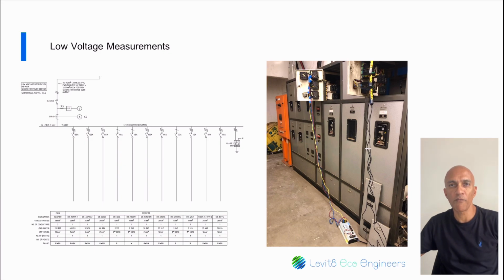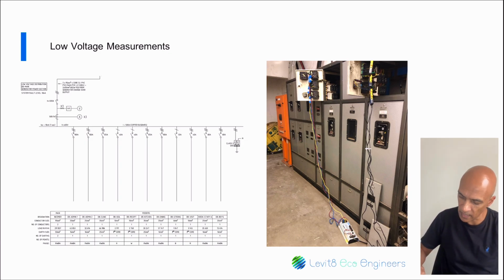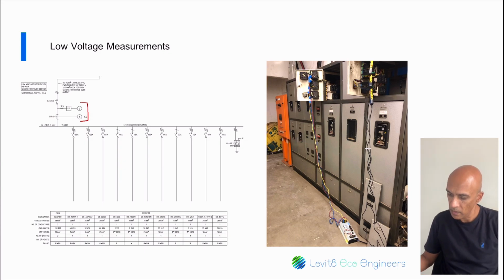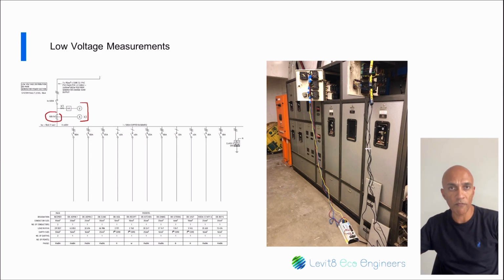As you can see, the above panel will be equipped with its own voltmeter and ammeters with a set of 500 to 5 amp CTs as in this example. So here we have the voltmeter and ammeters, and we have the CTs with 500 to 5 ratio. In this case, if you were to measure the main incoming supply, you could use the current clamps of your own, or you could use the transducers connected to the secondary side of the panel CTs. The best place would be onto the wires at the back of the ammeter, 5 amp maximum on this connection.